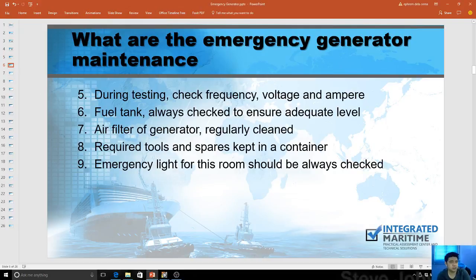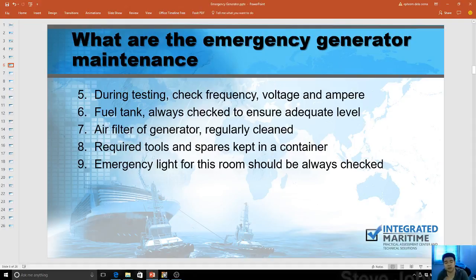During testing, check frequency, voltage, and ampere. Always check fuel tanks to ensure adequate level. Air filters for the generator should be regularly cleaned. Required tools and spares must be kept in a dedicated container on board — a separate box for spare parts and tools for the emergency generator, and they should not be removed from the room. Emergency lighting for this room should always be checked, because during an emergency, if the light in the emergency room is not lit, that's going to pose a very big problem.